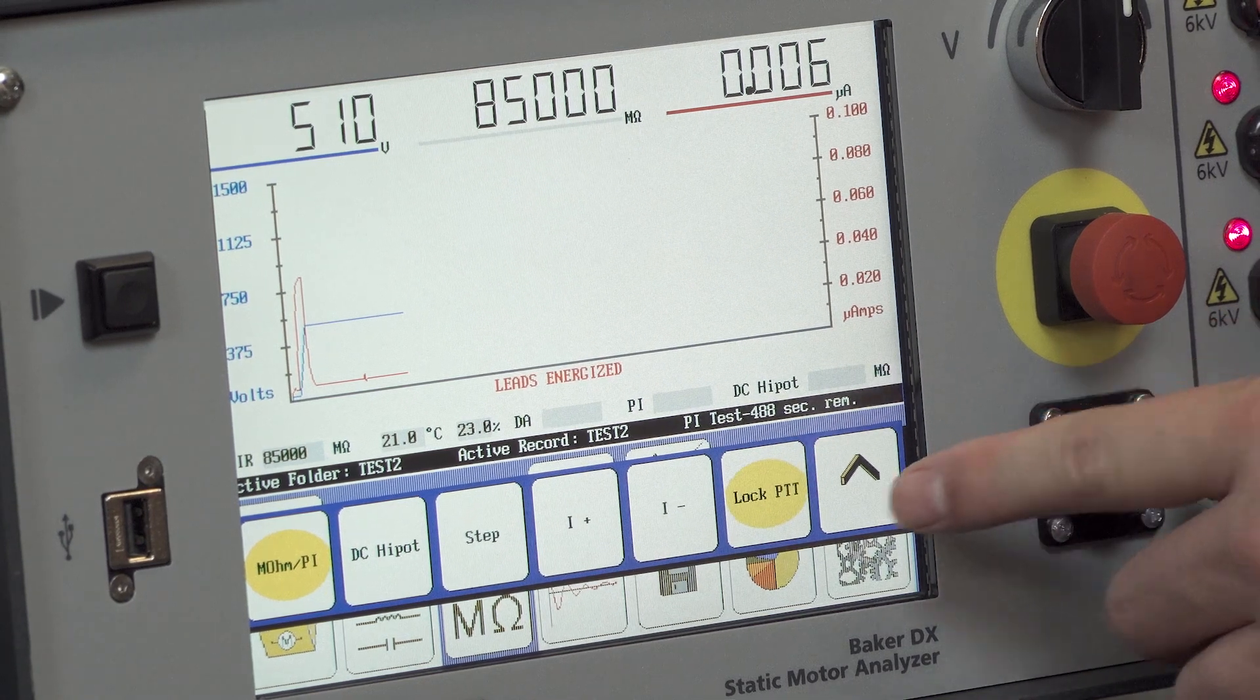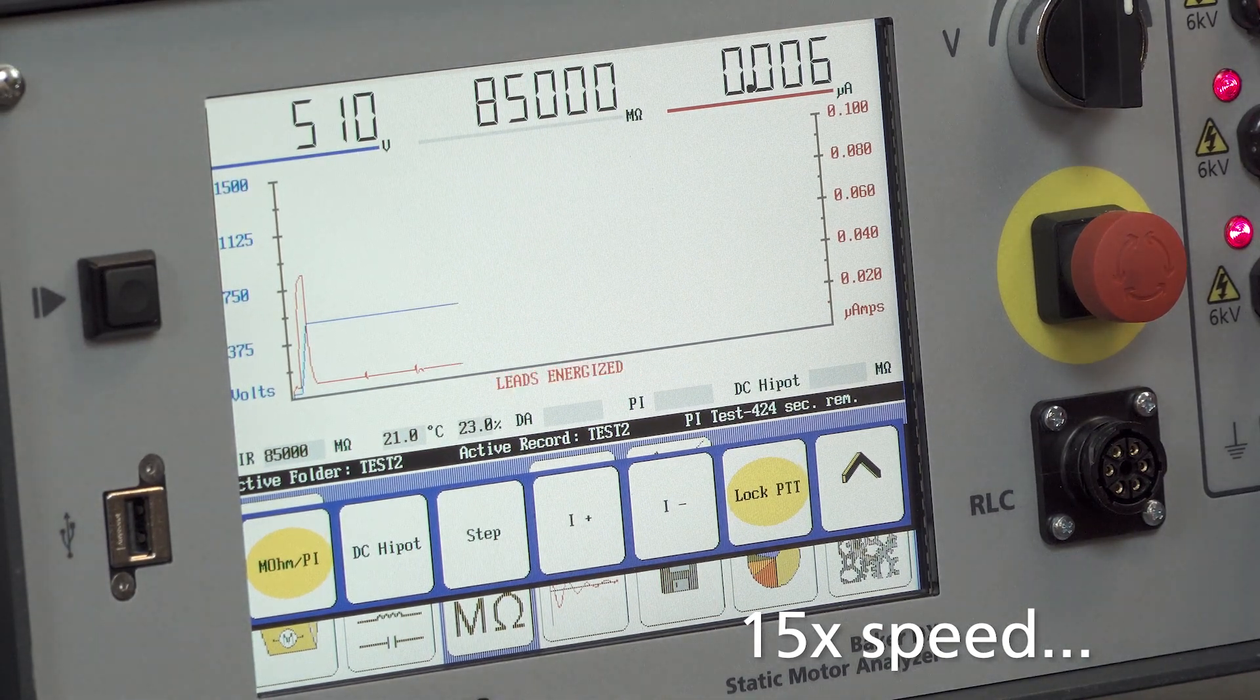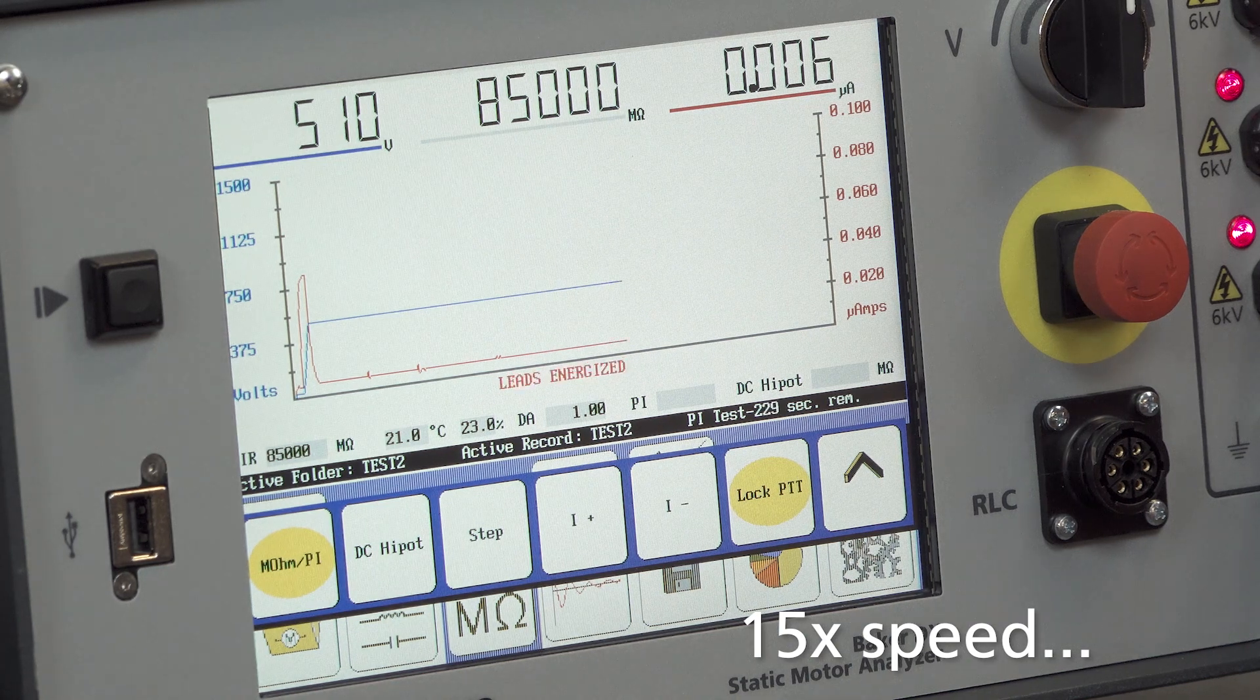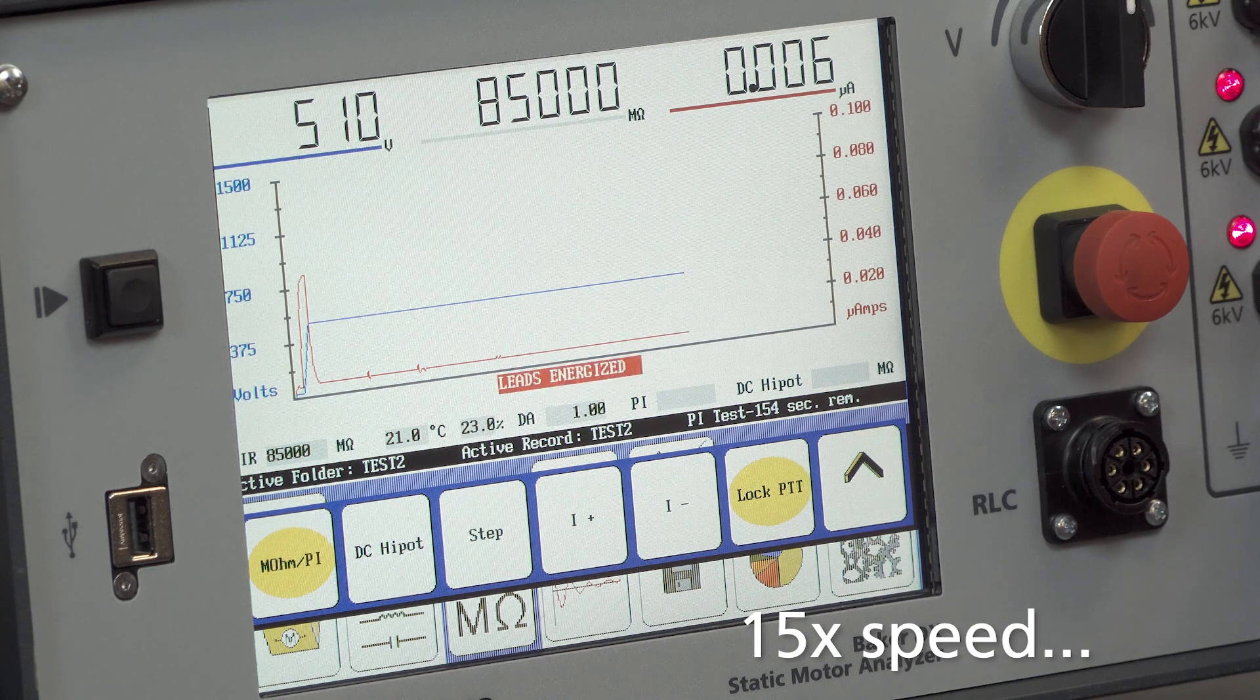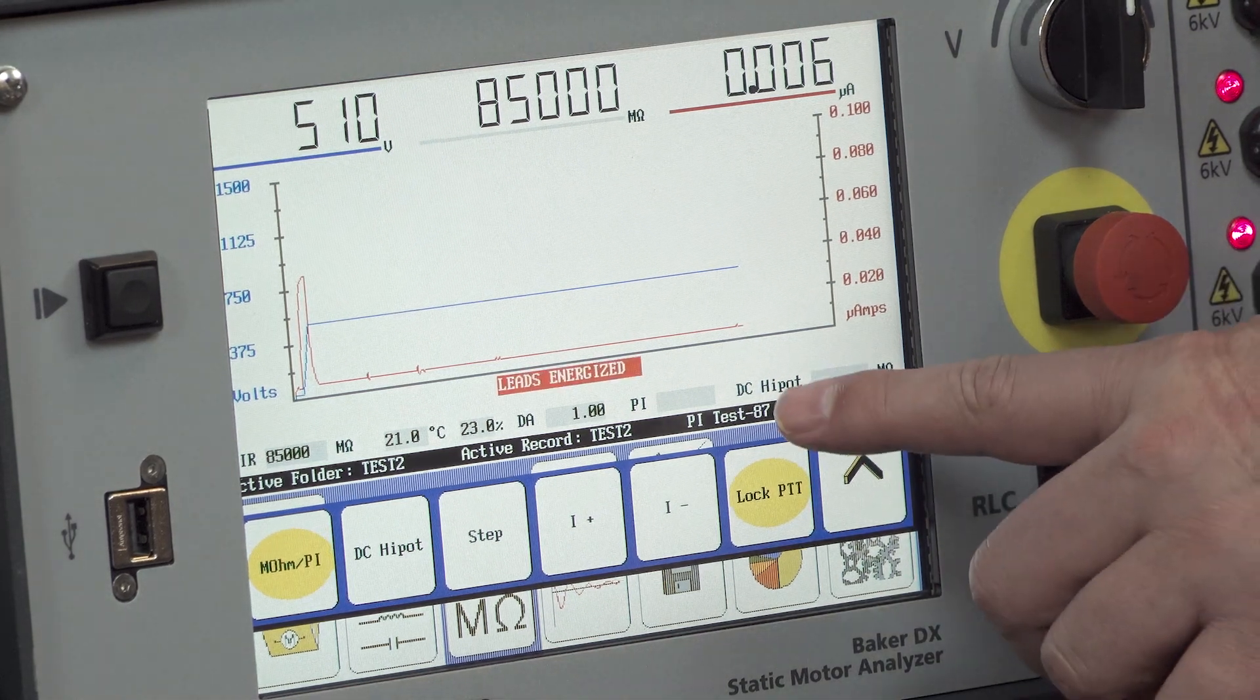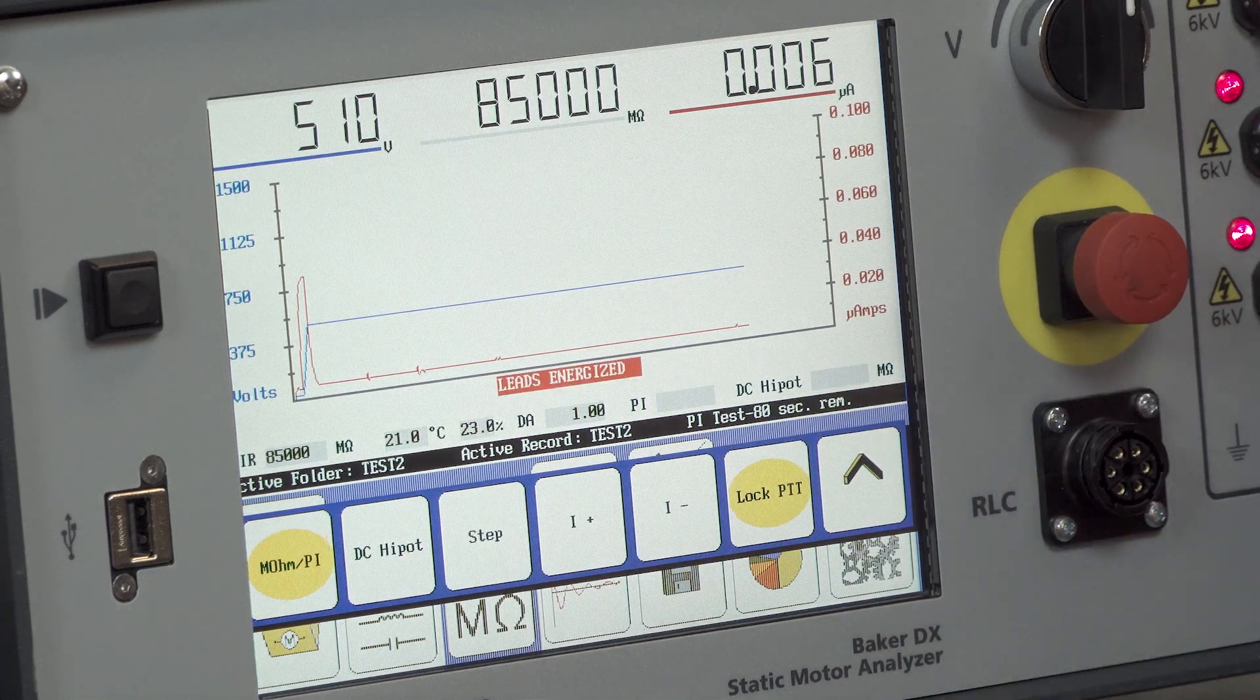Now we can see the PI test timer ticking down from 10 minutes or 600 seconds. As we're reaching the end of the PI test now, you can see our timer is almost complete. The DA ratio was populated, and of course once we complete the full 10 minutes, the PI ratio will be populated.